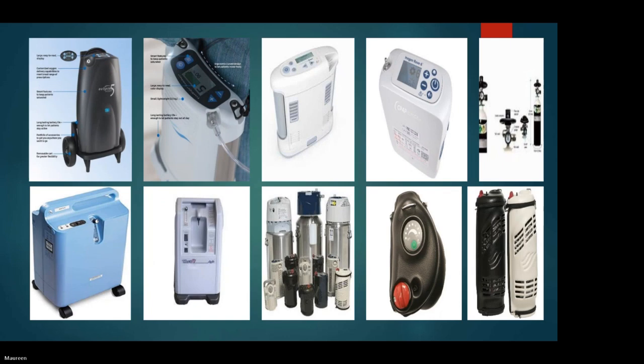The other machine on the bottom left-hand corner next to that, which is a grey machine, is also an oxygen concentrator, a static one, but it's a high-flow oxygen concentrator. And depending on the model, it can give you continual flow oxygen of between 9 to 10 litres per minute. Again, you can piggyback these machines to achieve up to 20 litres. You can piggyback 3 of them to get more than that. And sometimes that's done for patients who might be awaiting lung transplantation, who need high flow oxygen. So it's a noisier machine. That's the only drawback with it.